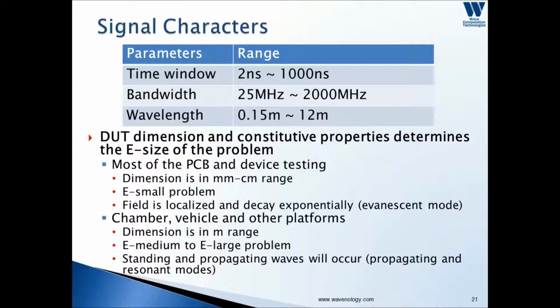Assuming all these excitations are applied in free space or air, the wavelength with the 6 types of pulses ranges from 15 centimeters to 12 meters. In general, if the object size is larger than a half of the wavelength, it is very likely that such a pulse will excite resonant waves within the object. Such resonances may lead to high emissions and interfere with its internal devices.